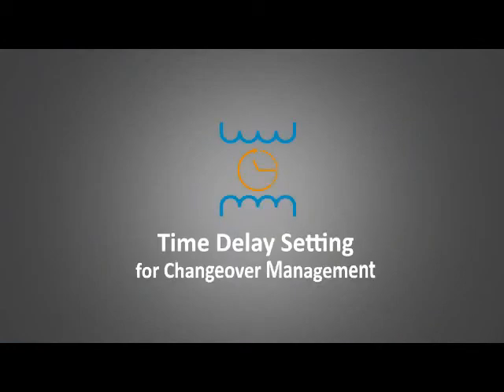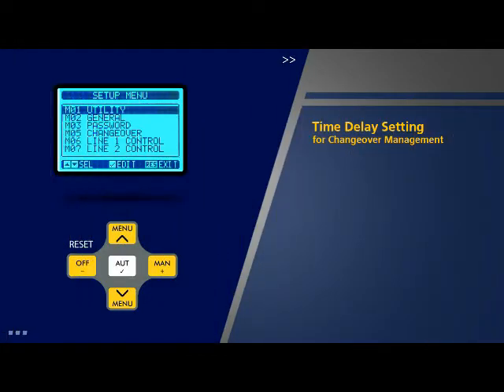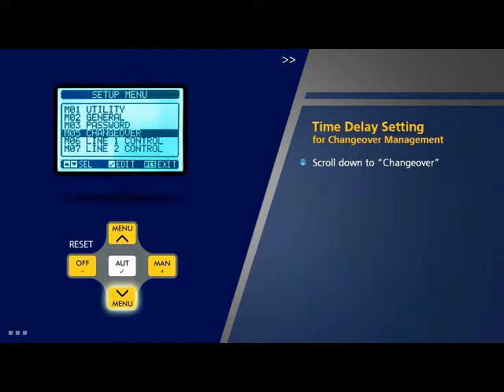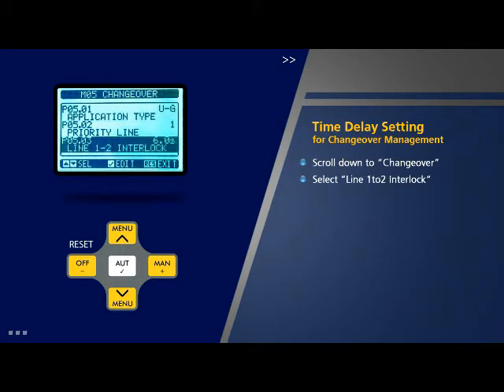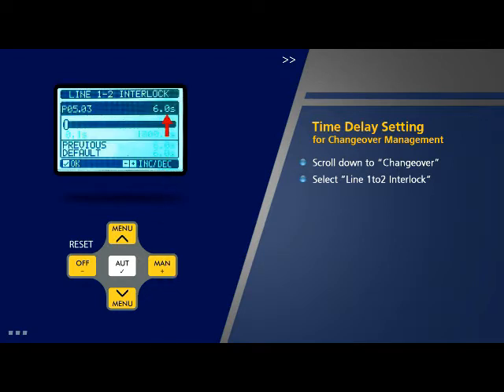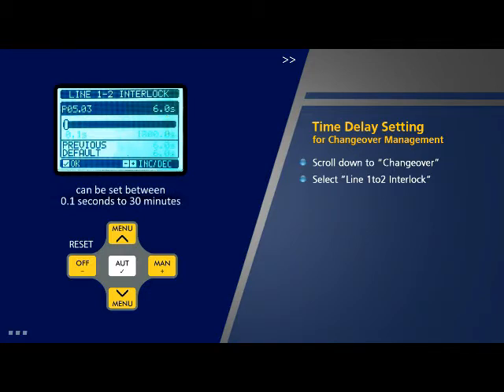Time delay setting for change over management: Scroll down to 'Change Over' in the setup menu and press OK. Select the third option on this page which is 'Line 1 to 2 Interlock'. This indicates the interlock time between line 1 and line 2, and is 6 seconds by default. The same can be changed and set to a value between 0.1 seconds to 30 minutes.